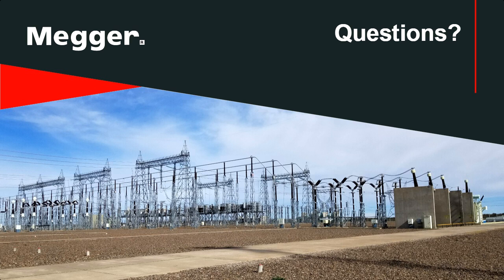Other than that, it's usually up to your maintenance protocols, typically every about 7 years. Some utilities do this every 5 years. So whenever you're talking about just doing a measurement, as far as timing goes, you want to do that as far as the full gamut of testing as well every 5 to 7 years at minimum. If not, then just follow your regular PM, whatever your company says, which is typically every PM cycle.